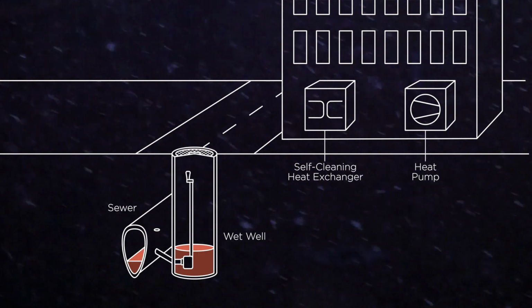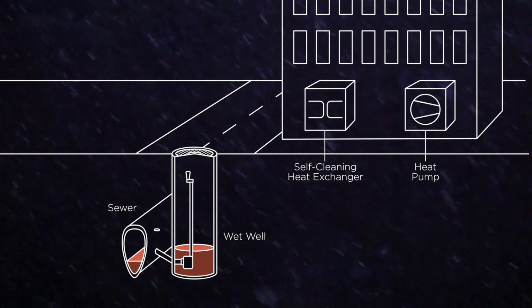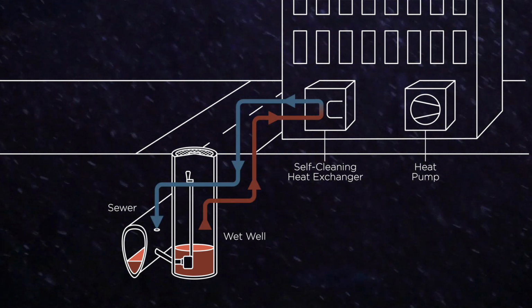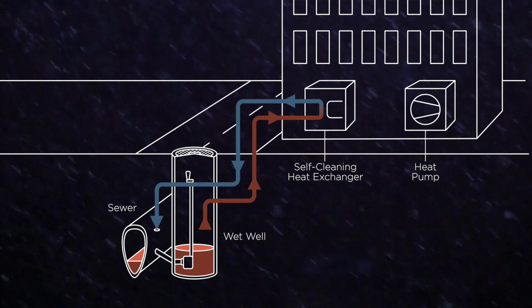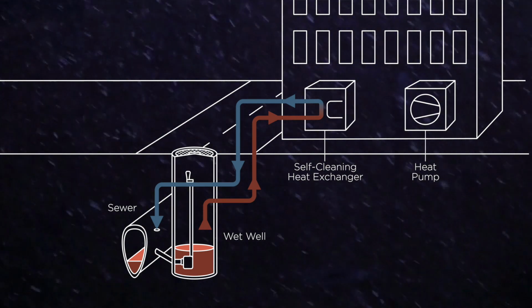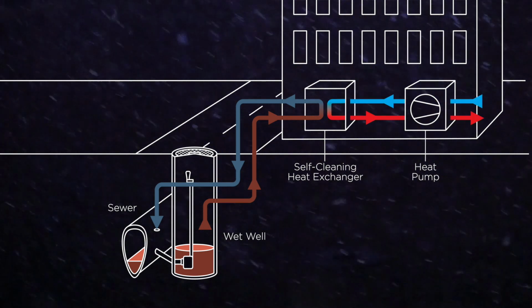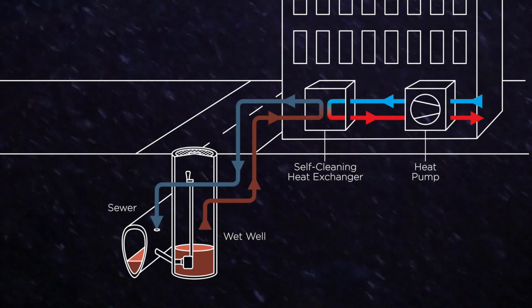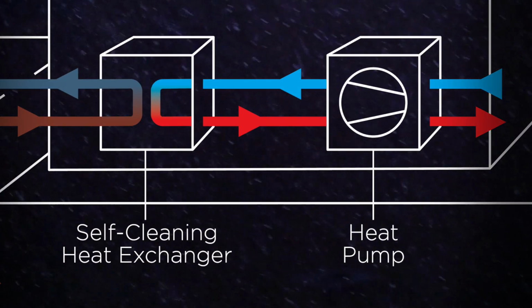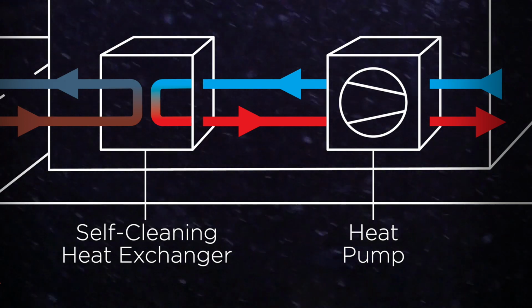So what if we diverted that sewer water into a wet well, then picked up that water, drove it through a heat exchanger that actually cleans itself—they've been using them for years for water treatment plants—and then transferred that heat to our mechanical systems. The wastewater doesn't actually touch the building systems, which is an important detail.